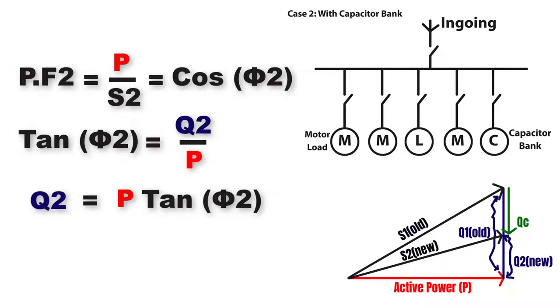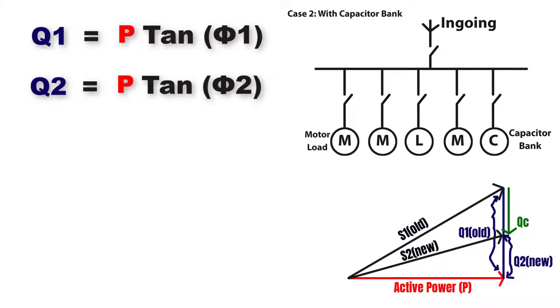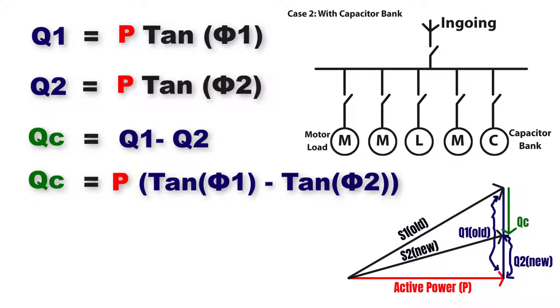If we subtract Q1 minus Q2 we get Qc, which is the required reactive power of the capacitors to improve the system. So Qc equals Q1 minus Q2, or P·tan(phi1) minus P·tan(phi2). Taking P as common: Qc equals P times (tan phi1 minus tan phi2).